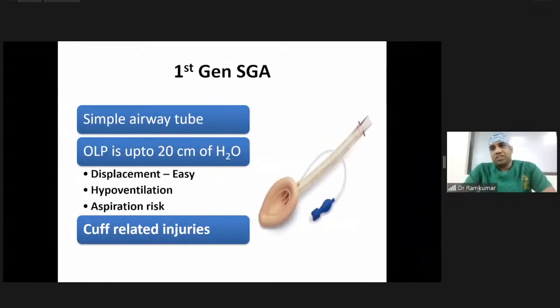What is the first generation device, and why is it slowly going out of practice? It is considered a simple airway tube, with a 15 mm airway connector at the top and a mask, which is silicone or PVC, in a disposable type with an epiglottic aperture bar. This epiglottic aperture bar prevents the epiglottis from obstructing ventilation. So this device has a poor or low oropharyngeal leak pressure.